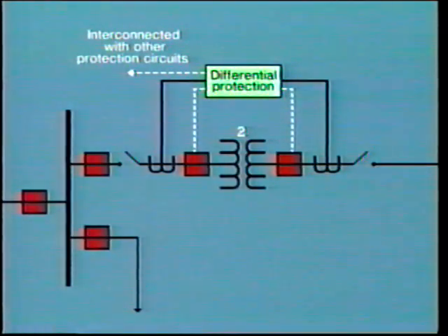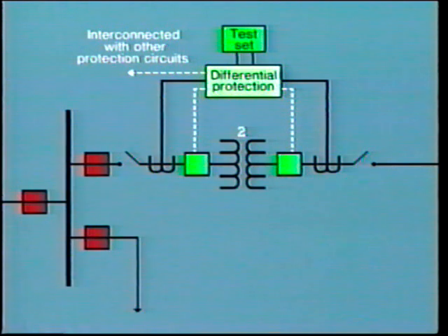So with this assumption, he connected the test leads to the relay and applied pickup current. The resultant operation of the differential relay inadvertently tripped several other breakers on the bus. This instance shows the problem of taking shortcuts. We know that this may be done in good faith in order to save time and get the job done. But in this particular case, it would have been better if our technician had looked for the correct tool and removed the trip wires from the relay before proceeding.